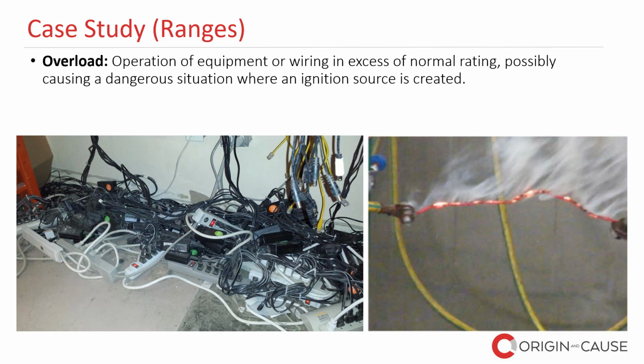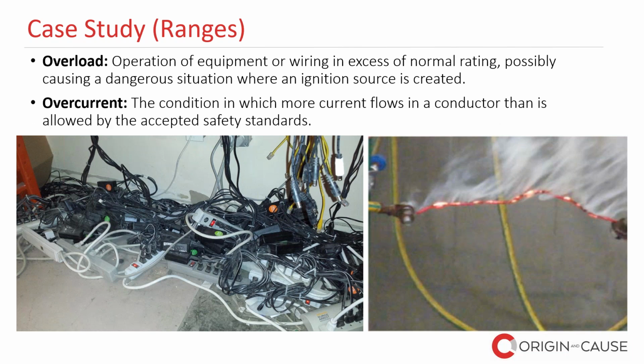Continuing on, some of the possible causes of electrical failures resulting from misuse can be from too much current or damaging the cables. One such way involves overload, which is the operation of the equipment or wiring in excess of its normal rating, possibly causing a dangerous situation where an ignition source is created. This, in fact, can result in overcurrent, which is the condition in which more current flows in a conductor than is allowed by the accepted safety standards. In the left photo, which you can see right here, we see an extreme example of overload in a commercial office building. Now, this hasn't caused a fire, but the possibility remains. The right photo is from a test we conducted where we increased the current beyond the rating of the cable. This caused the cable to overheat and ignite the insulation surrounding it.